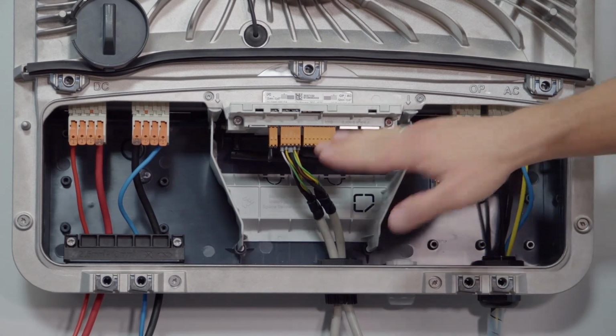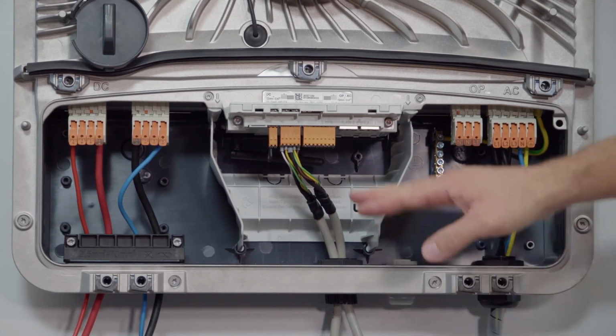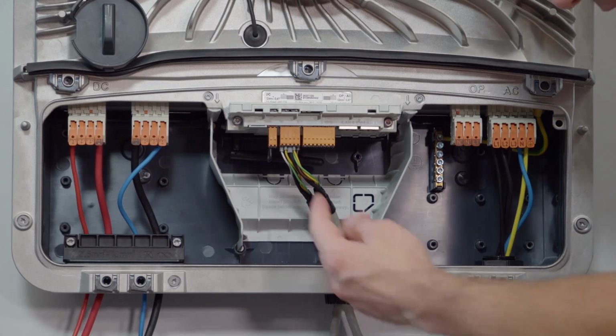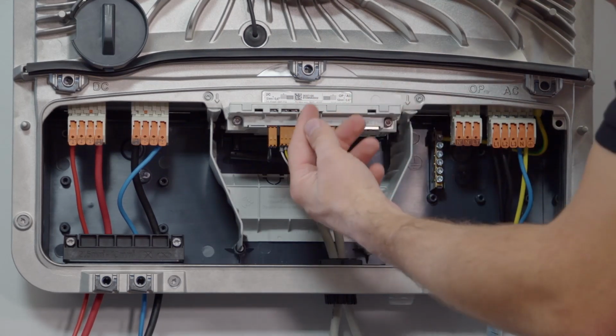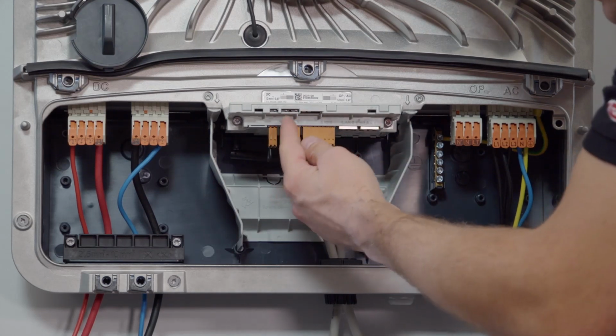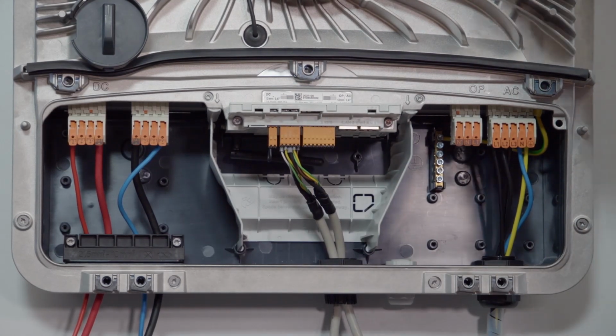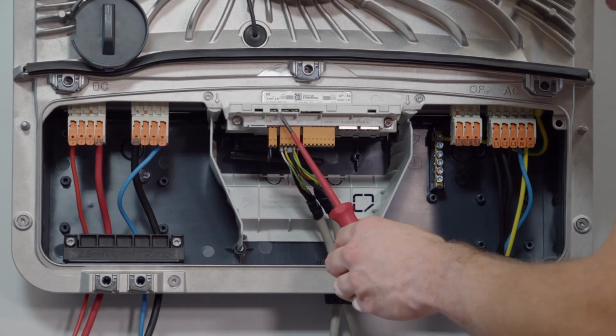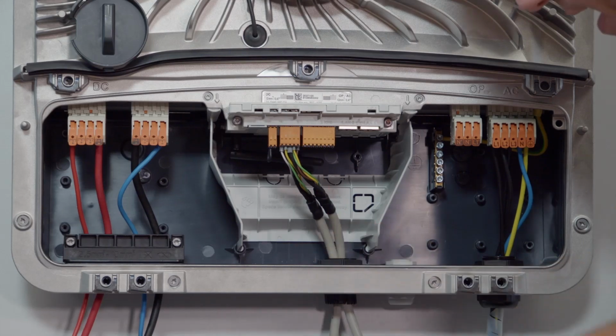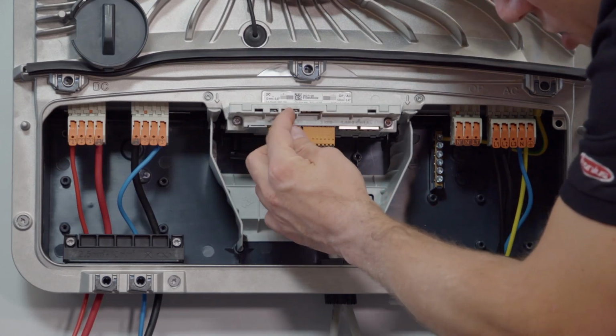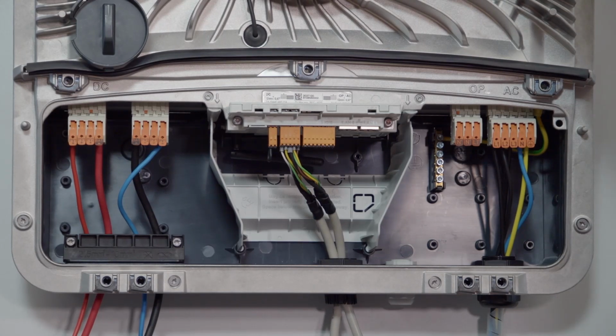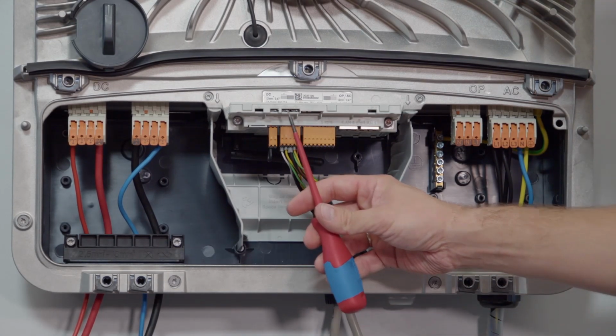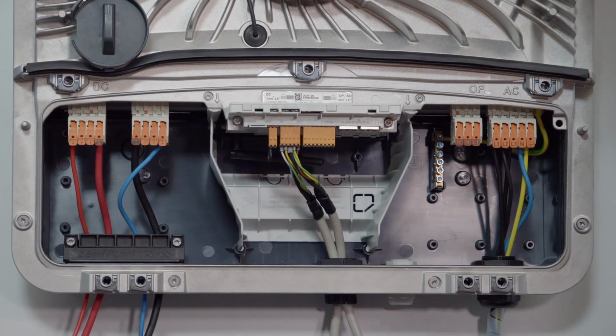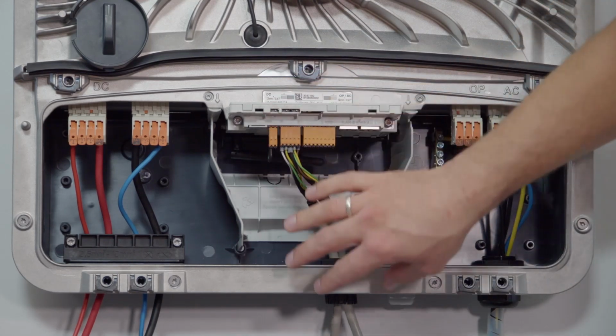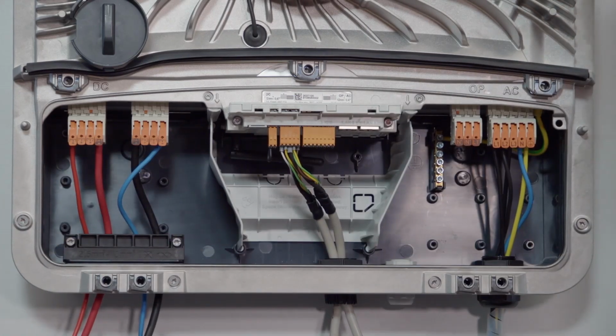And the last thing that we want to do in here is the termination resistance, the 120 ohm termination resistance. Since we installed the smart meter to MB1, we now have installed the LG Chem system to MB0. And as you can see up below here, we have a termination resistance, we have this little dip switch, and therefore we need to bring the dip switch into position 1 and activate the MB0 communication, and therefore activate the 120 ohm resistance here at the GEN24 Plus. After that we go with our data communication cable further to the LG system, and therefore we can do the data communication directly in the LG.